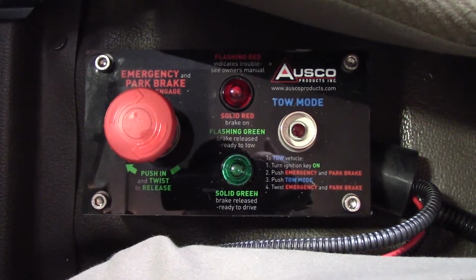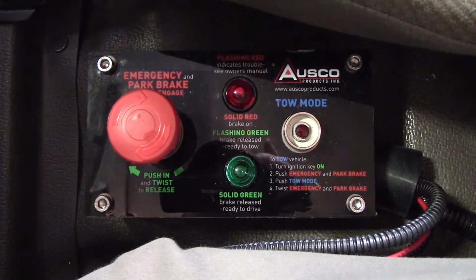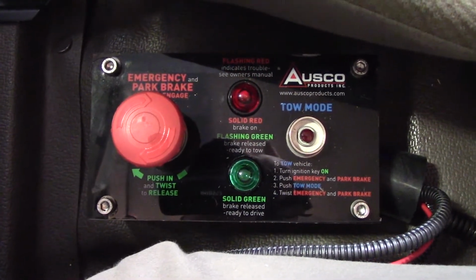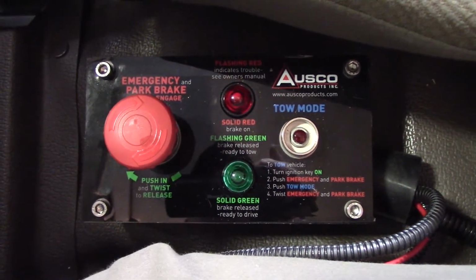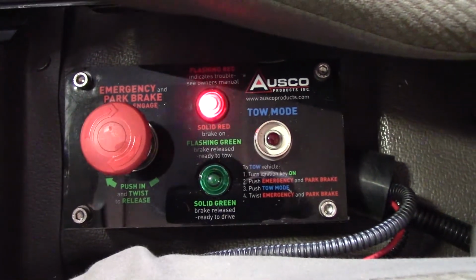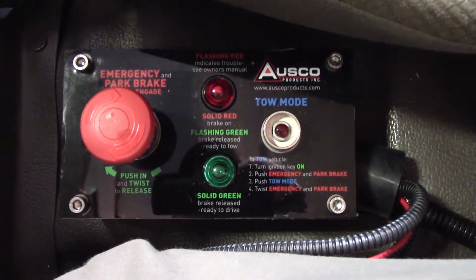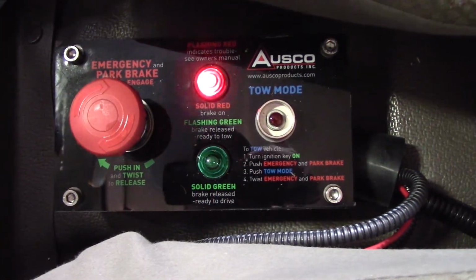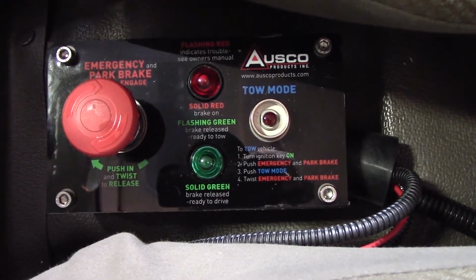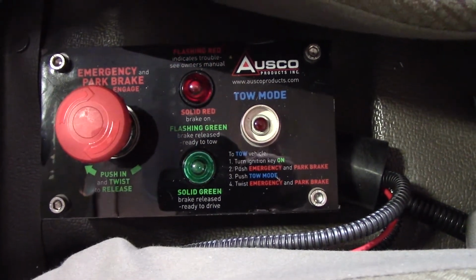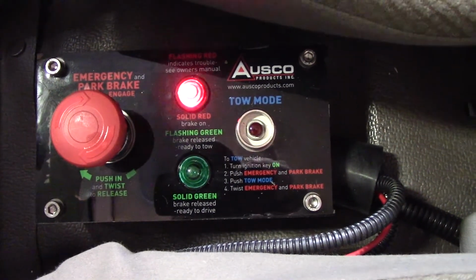The second error code is when the red light flashes 2 times, meaning the system is not achieving hydraulic pressure within 30 seconds. In other words, the system may have a leak and the vehicle cannot be driven, so please seek service.